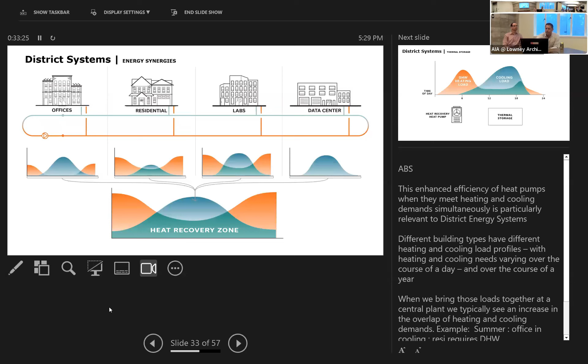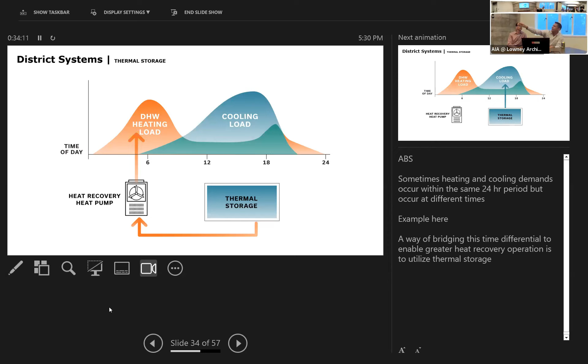This is another example where quite often in buildings we'll find a scenario where you've got heating and cooling that occurs in the same 24-hour period, but they're sort of separated by 6 or 7 hours. So you'll have a domestic hot water load in the morning, maybe the showers and food production, and then in the afternoon, the sun's out, you've got a cooling load. And a way in which you could take advantage of this is by introducing thermal storage. So in this example here, the heat pump is pulling heat out of the thermal storage tank, creating chilled water. And at the same time you're meeting that domestic hot water heating load. So that's heat recovery mode, the COP is 7.